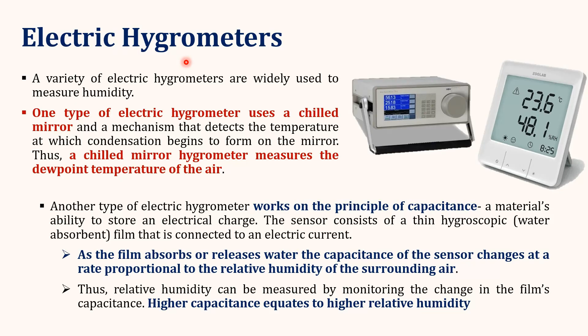Another type of electric hygrometer works on the principle of capacitance, a material's ability to store an electric charge. This sensor consists of a thin hygroscopic film which is connected to an electric current. And as this film absorbs or releases the water, the capacitance of the sensor changes at a rate which is proportional to the relative humidity of the surrounding air. Thus, the relative humidity can be measured by monitoring the changes in the film's capacitance. These are the two examples within the electric hygrometer, but there are various others which work on different principles. Some of them use higher technologies like thermistors.